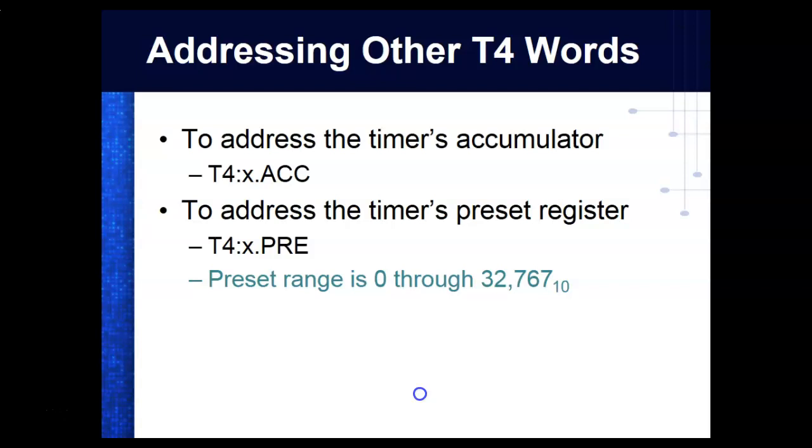16-bit words in there. One thing that I didn't deal with is the largest number we can put in there is 32,767, because these are signed integers. So this is the largest thing that we can put in there. And this would be, if I use a multiplier of 1, this would be 32,767 seconds. Anybody know why we're limited to this? Yeah, because it's signed integers, is what it is.